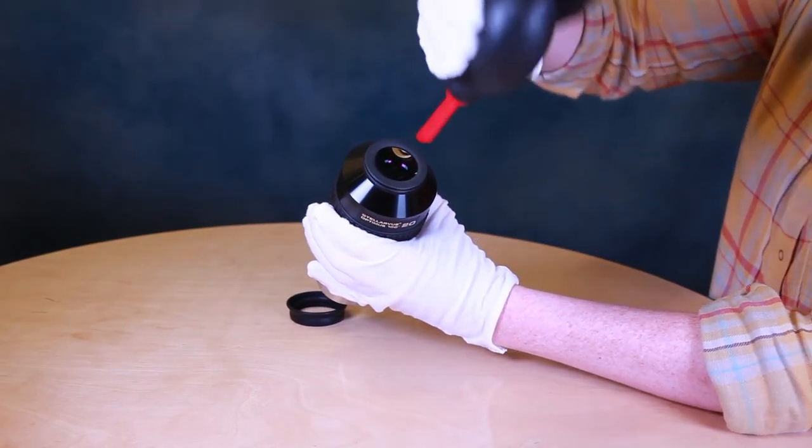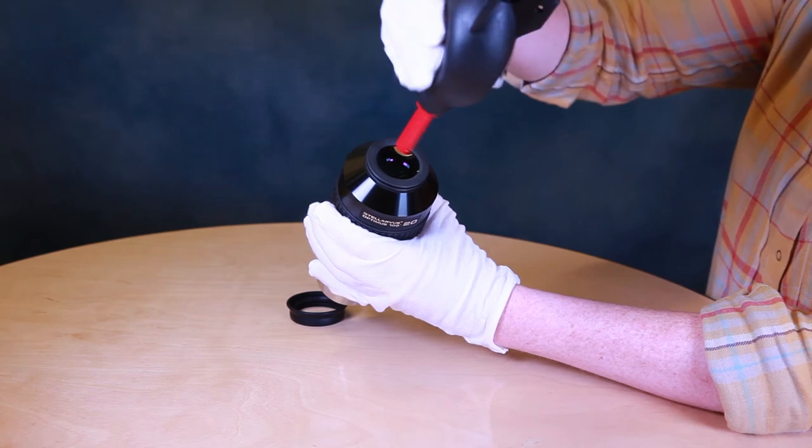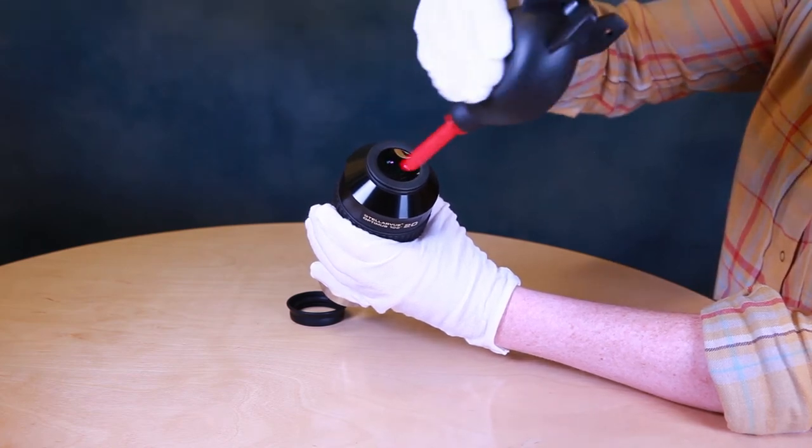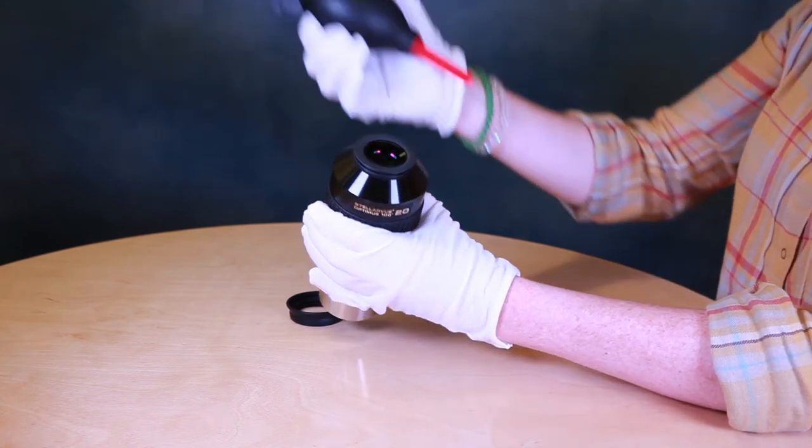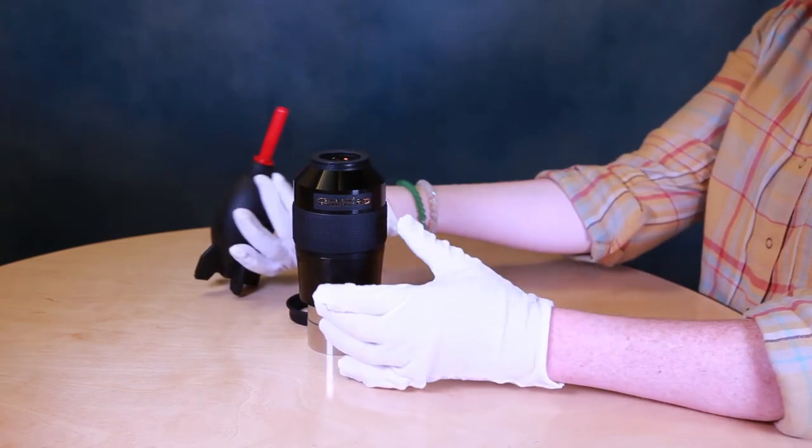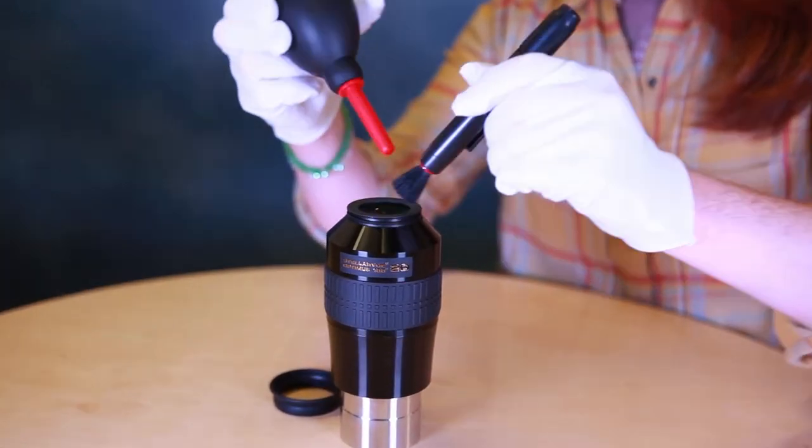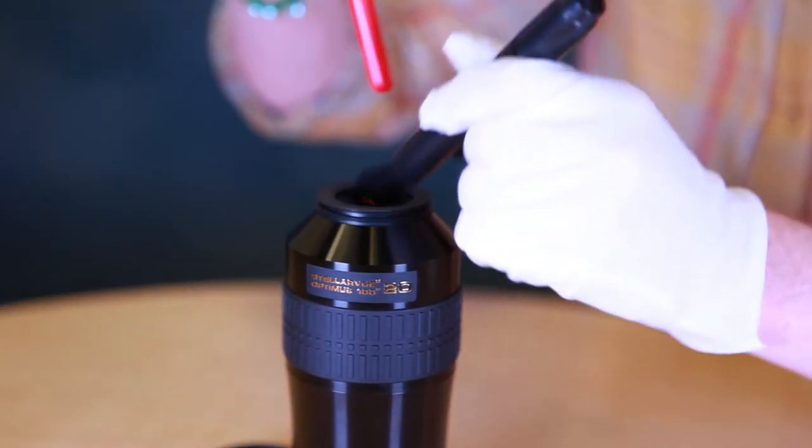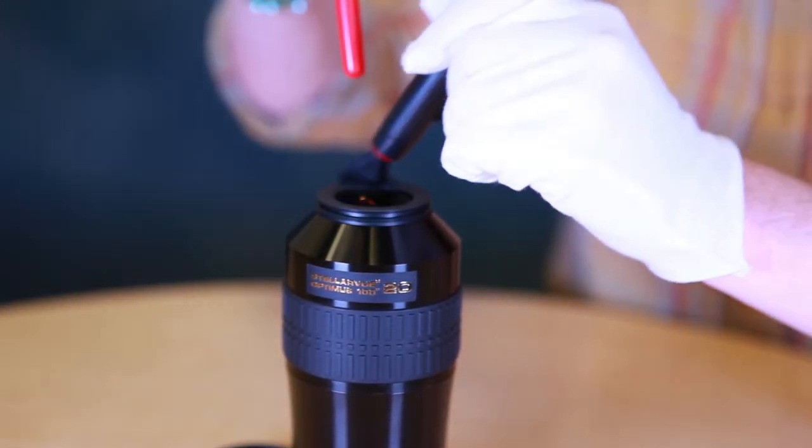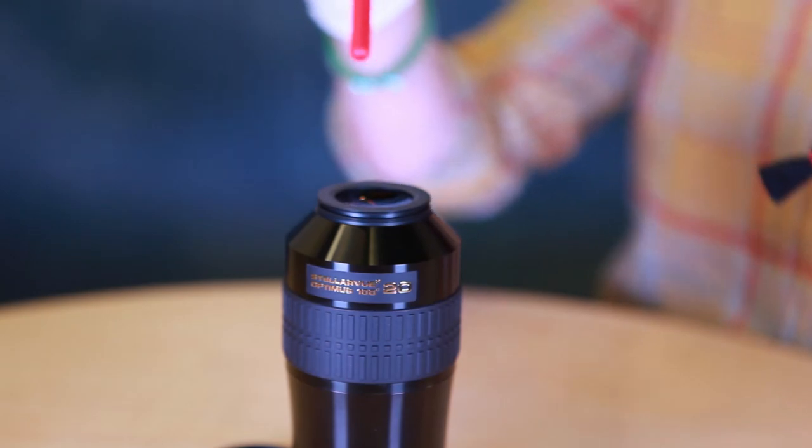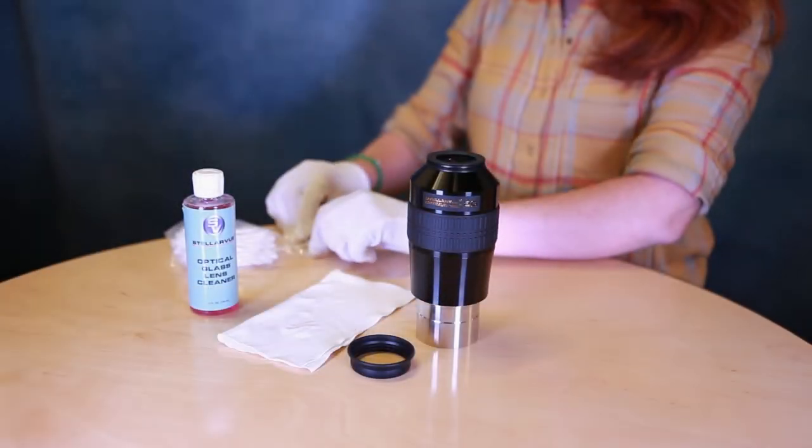Start by using your bulb blower. Blow off all of the loose dust on the lens surface. But don't just stop there. Use your camel hair or lens pen brush with the bulb blower to remove all of the loose material. Now you can go ahead and clean the optical surface.